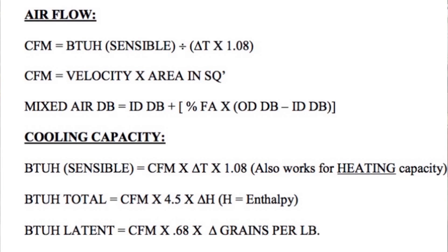Let's work through an example. If you have 1000 CFM — typical of a 2.5-ton machine at 400 CFM per ton — multiply that by 4.5, then by a delta H of 6.7, you get 30,150 BTU. The actual average delta H would be 6.67, or six and two-thirds — we just round up to 6.7. So what can you assume if your delta H is higher or lower than 6.7?